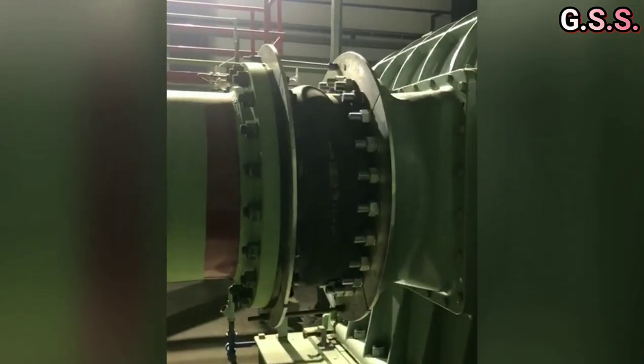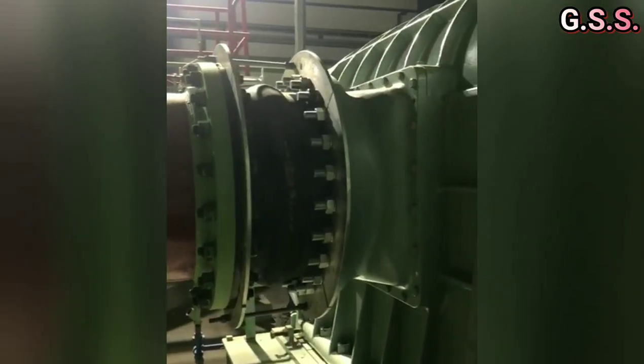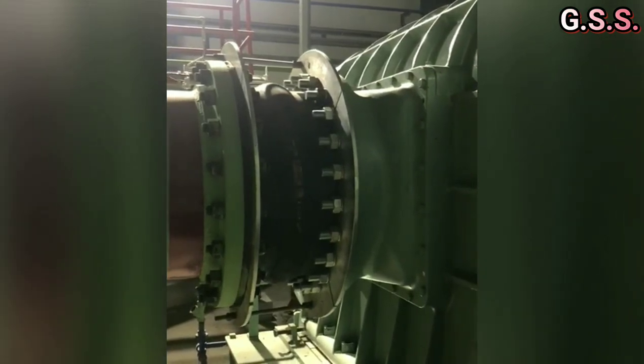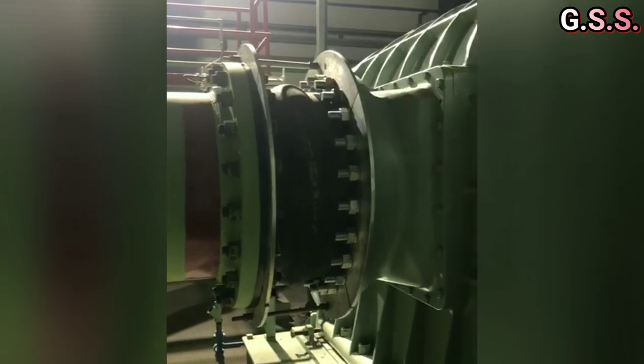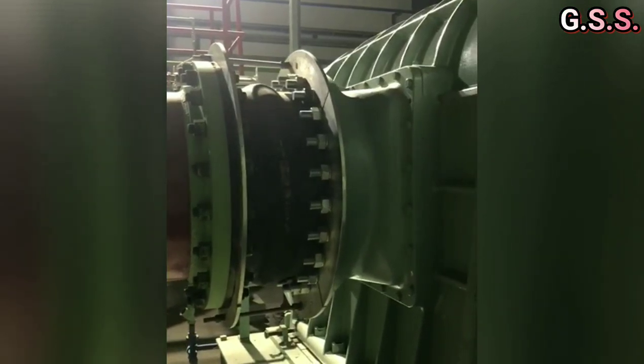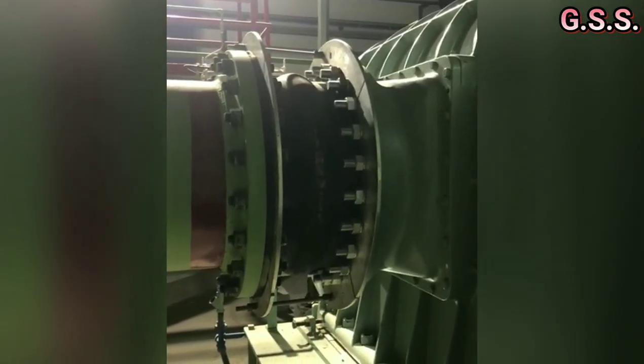Now you can see one 24 inch rubber bellow installation at air blower discharge line at 1 bar gauge pressure. Tie rod nuts and lock nuts kept tight and the system is safe.